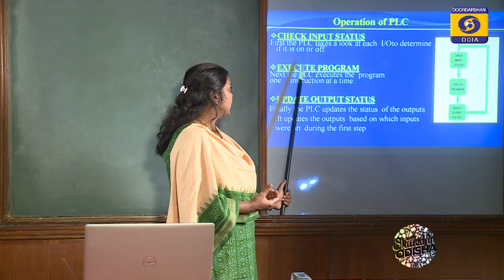So how does the control of a machine take place with this PLC? First, the input status will be checked, and the operation program that controls the machineries is performed in various stages: input scan, then program scan, then output scan. In the input scan, the IO modules sense the status of input or field devices. Then the execution scan: in the execution scan, the total control program is executed by the processor, and it updates the output modules, which will send a control signal to control the machineries. And these are the scans I was talking about.